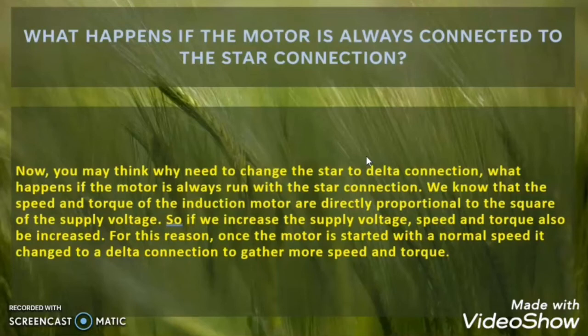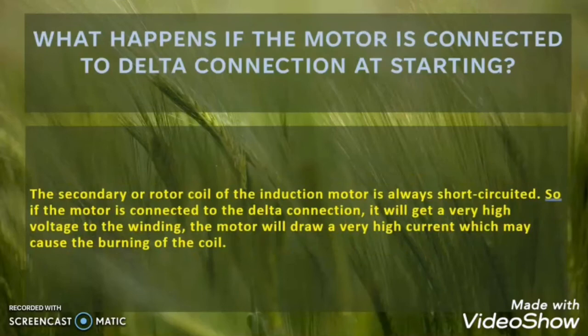Now another question arises: can we run the motor throughout in the delta configuration, without starting in star at all? No, in that case also the problem will not be solved. As I told you, in the delta configuration the voltage across the winding is the rated voltage. Due to the rated voltage there will be a huge current in the winding, which will result in a high inrush current at the time of starting. So the problem remains the same.